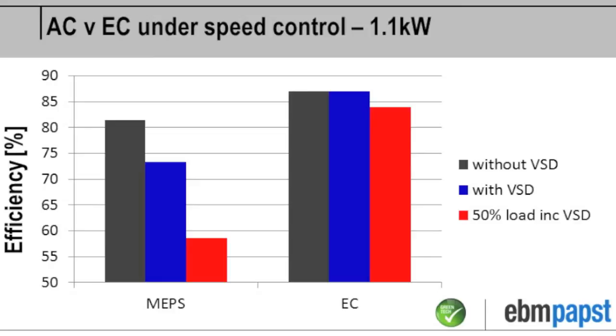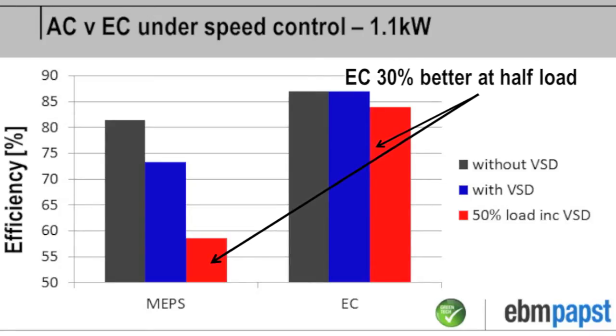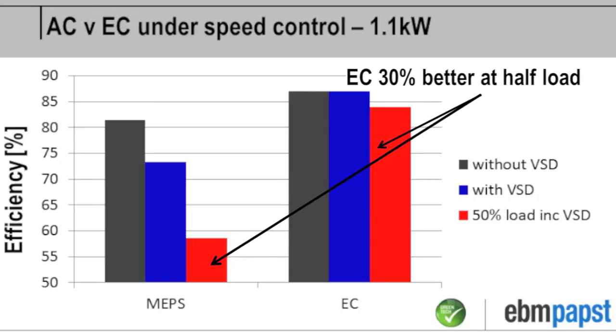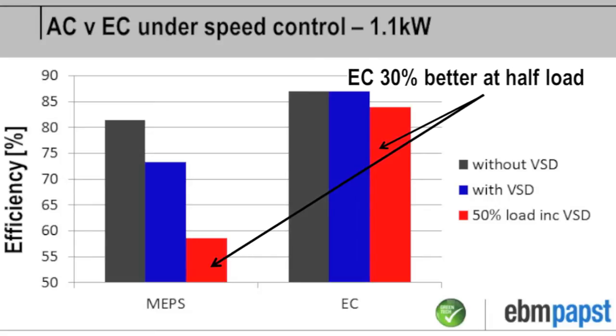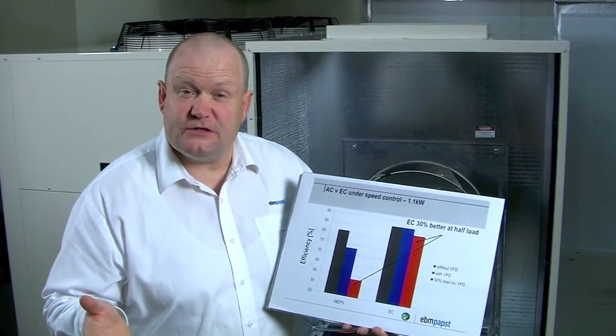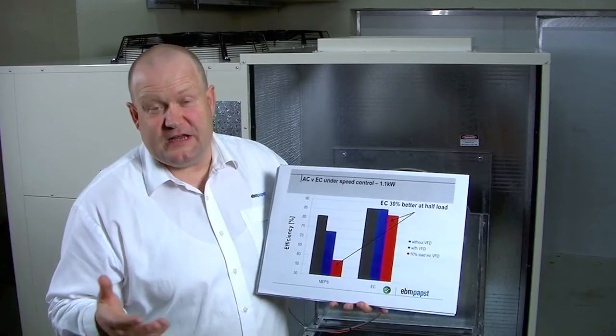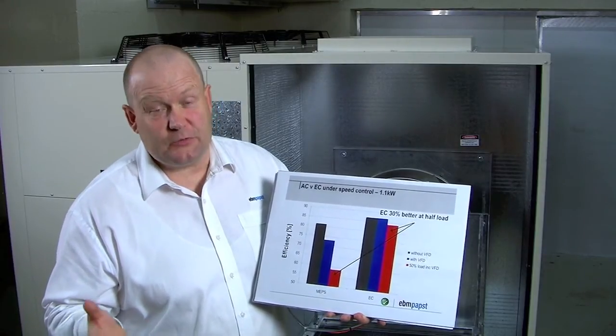So here I've charted the efficiency of the two systems at 50 percent speed and you can see the dramatic drop off in the efficiency of the AC VSD couple in comparison to the EC product. The EC product stays at high efficiency across the whole of its speed range and this is really important. This means if you're looking to use speed control as a strategy for reducing your power consumption then EC and permanent magnet motor products are the products to choose.